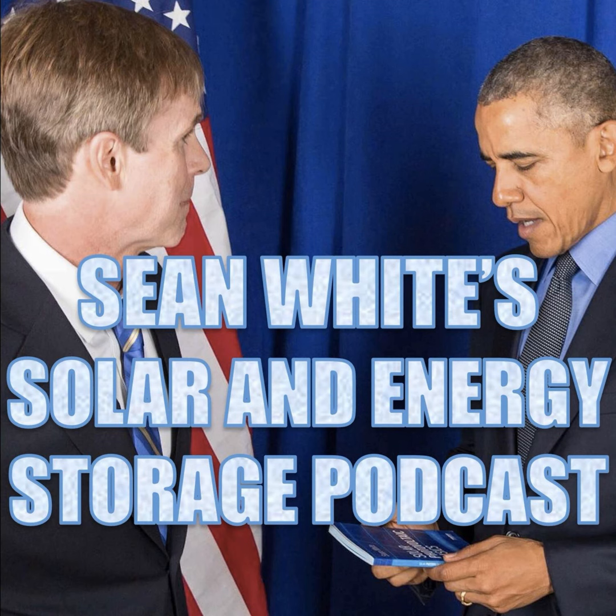690.31C, cables. PV wire or cable and distributed generation DG cable shall be listed. The PV wire listing is UL 4703 and the DG cable is UL 3003. And now we're going for a text box. UL listing numbers in this industry are related. The UL listing for PV is UL 1703, or 61730 more recently, see below.